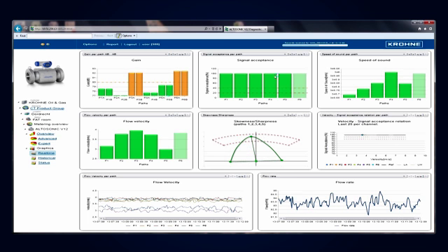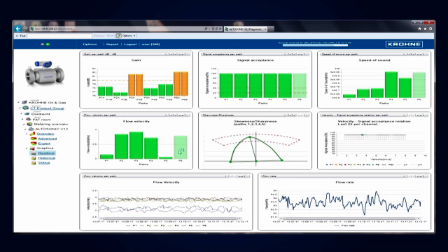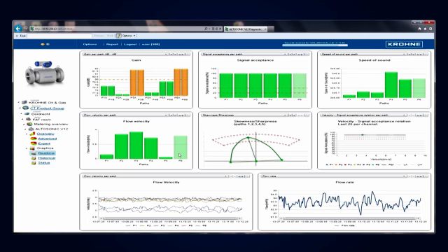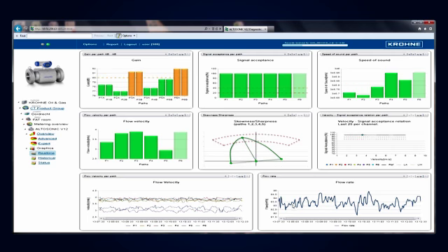Other items we see are signal acceptance, speed of sound, flow velocity in the meter. You see that in every case path 6 has a lighter color. The reason is that path 6 is not used for flow measurement. It's only used for diagnostics, so we gave it a lighter color. We see here the flow profile, the signal acceptance, flow velocity per path and overall flow rate. As with the other screens, all those screens are user modifiable.